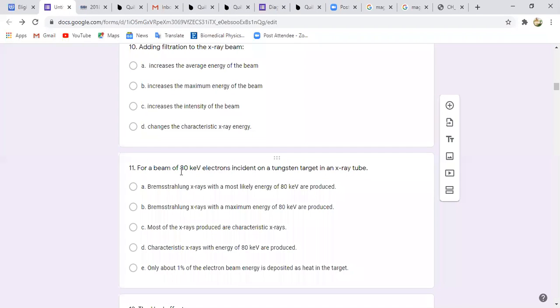So to translate to energy, the most energetic electrons will have this energy; others will have a lower energy. The Bremsstrahlung will have a maximum energy of 80 keV. And depending on the efficiency of the machine, we can have from 20 to 80, or 30 to 80, or 40 to 80, as the case may be. That depends on the efficiency of the machine and the filtration.